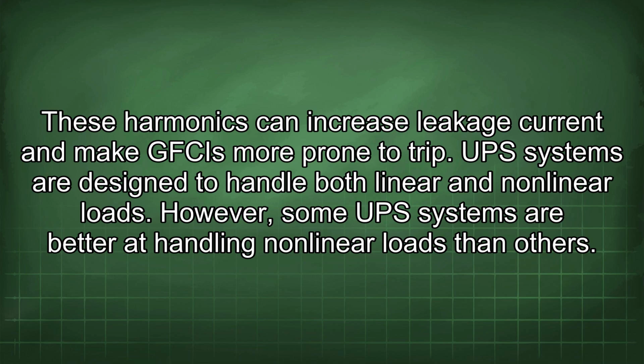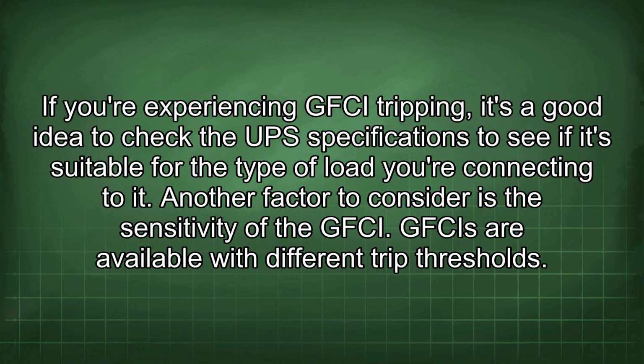UPS systems are designed to handle both linear and non-linear loads. However, some UPS systems are better at handling non-linear loads than others. If you're experiencing GFCI tripping, it's a good idea to check the UPS specifications to see if it's suitable for the type of load you're connecting to it.